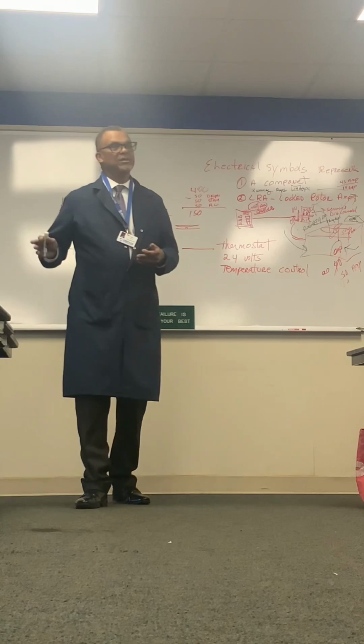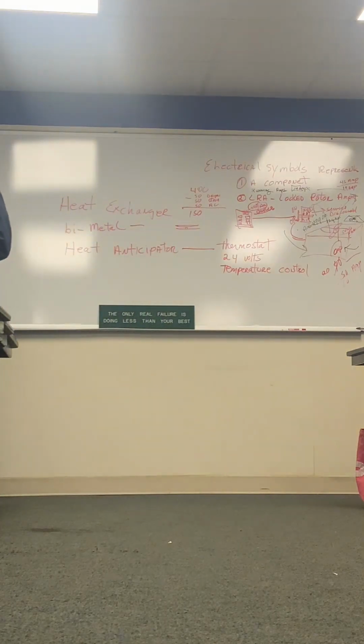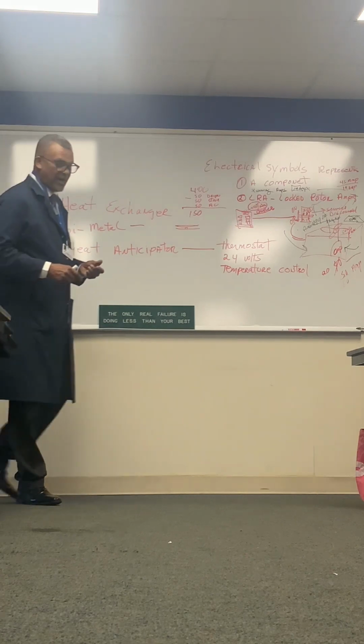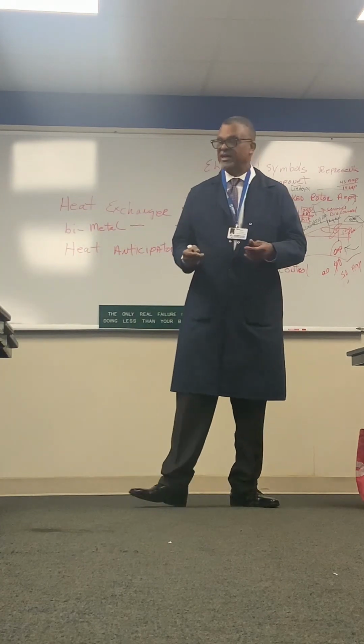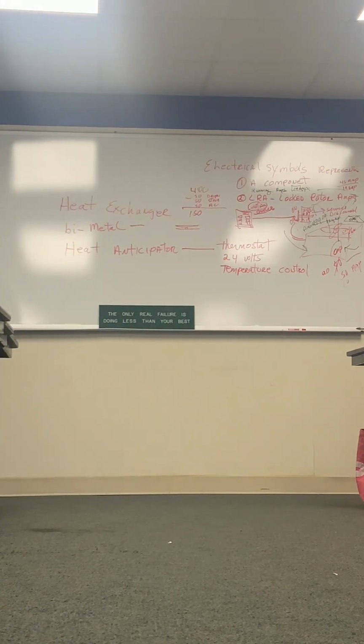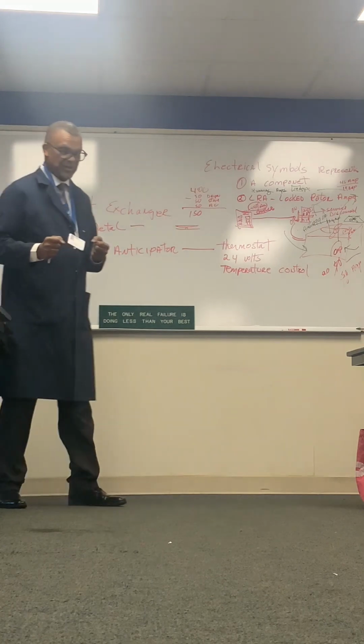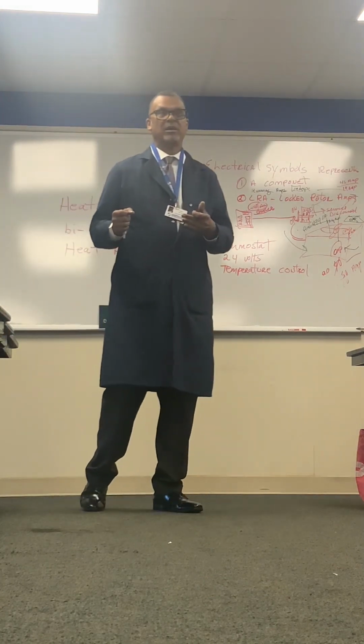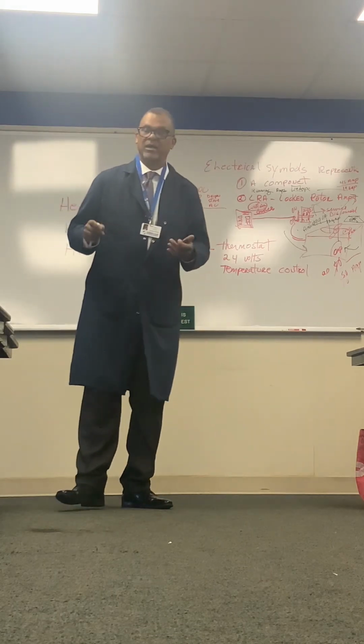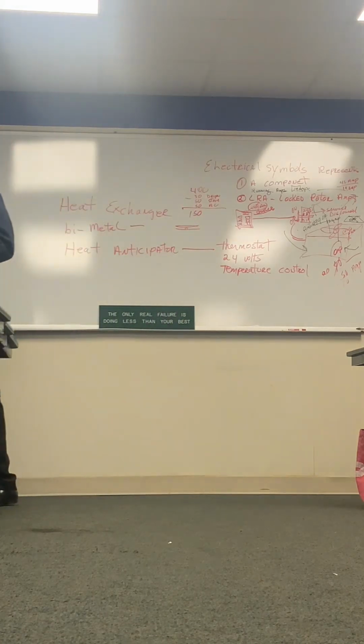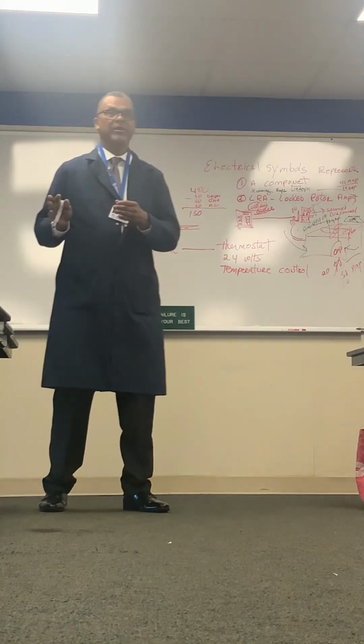So when it returns back to the compressor, it'll return to the compressor and go through the metering device, which is TXV in this case, or piston, or cap tube, which is a restrictor. You'll learn about that as well. And it'll come back as a liquid. And as it is restricted in the metering device, it will depressurize it and make it colder.